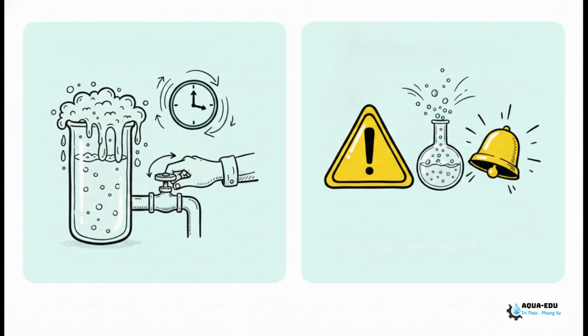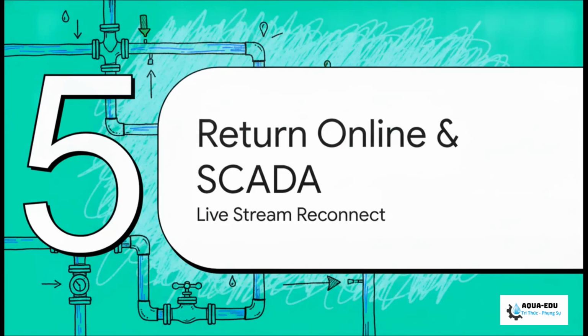You might run into a few roadblocks at this stage, so let's compare two really common errors. If you get a TOC overflow error, it means the sample has way too much TOC. You'll need to jump into the menu to either reduce your sample volume or increase the sparge time. On the flip side, if you see high CO2 in base, you need to check your alkaline reagents and your base CO2 alarm settings. Let's hit Section 5, Returning Online and SCADA.